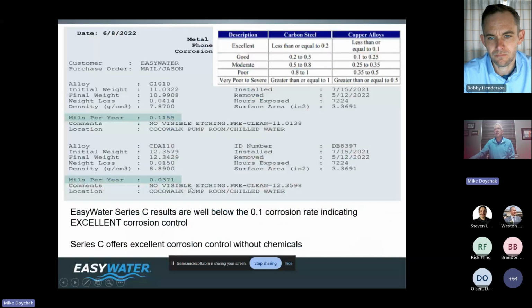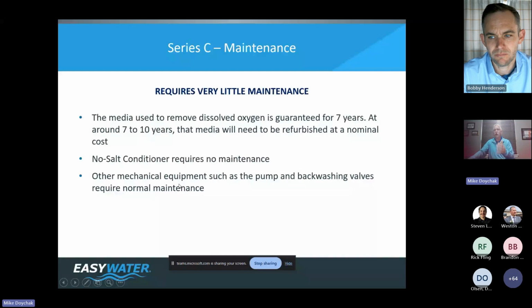Corrosion coupon test. Here's what those look like. Your owners, what would they look for? If they're looking for excellent performance with carbon steel, they're going to look for less than or equal to 0.2 mils per year. We're about half of that at 0.1155. Copper, less than or equal to 0.1. We're about a third of that at 0.0371, indicating excellent corrosion control.